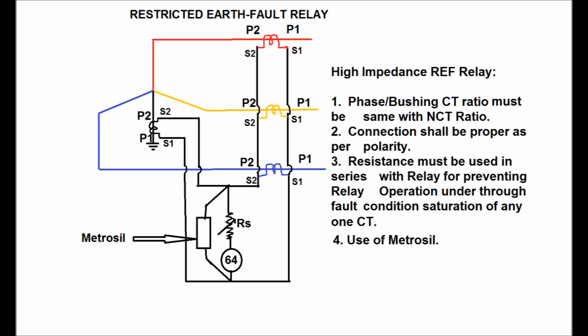Before going through this video, first let's discuss what the criteria are for high impedance REF relay. The criteria are that all the CT ratios, that is phase or bushing CT ratio, must be the same as that of the NCT ratio. Also the knee point voltage of each CT shall be the same.